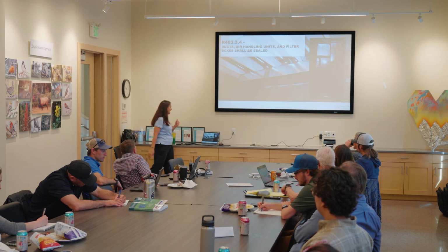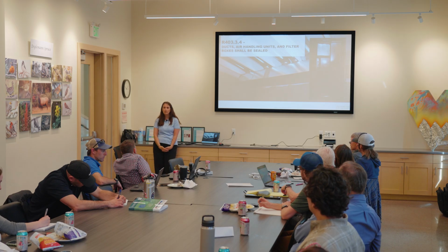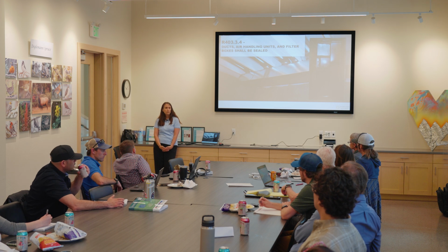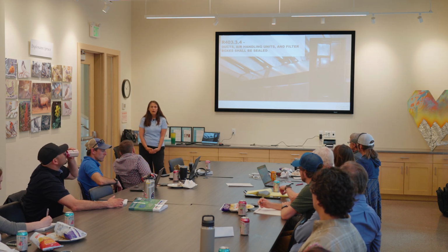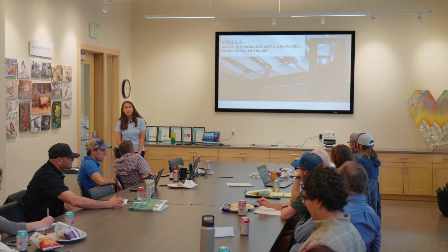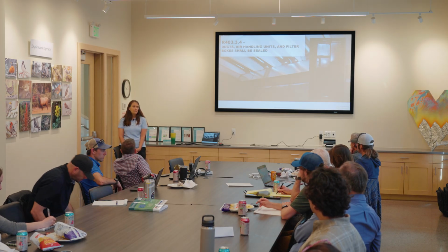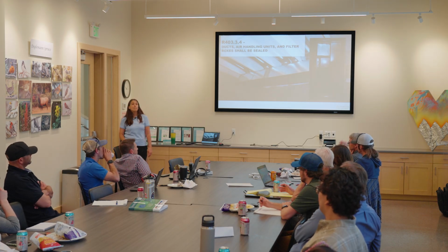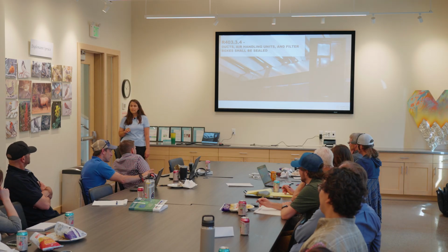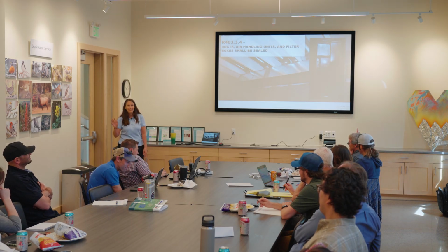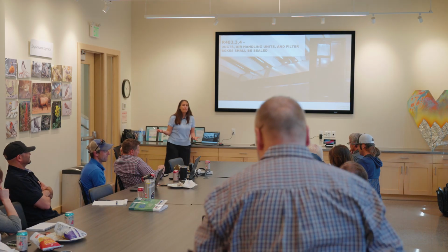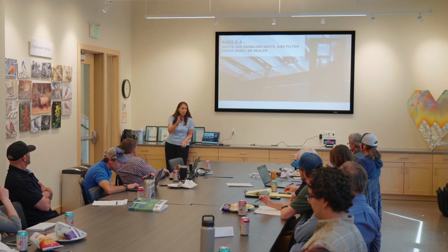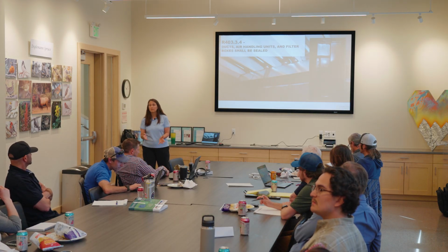Now, how many of you see notes on your plans that talk about sealing up ductwork? A few of you, yeah. That's one that I am perfectly okay with them providing a note. I don't want it buried in the general notes because how many of you read the general notes? Okay, how many of you, when you're not being a plans examiner, read the general notes? All right, so a couple of people, but the reality is I want to see a note somewhere outside of the general boilerplate notes because half the time those notes are incorrect anyway.